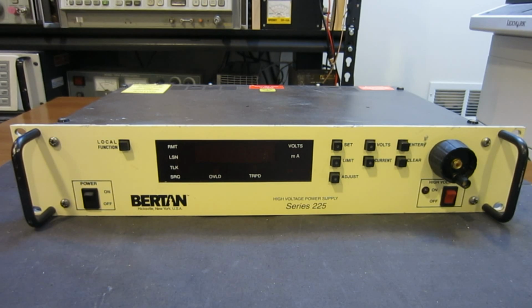Now, before I get started, I would like to stress that this is a high voltage power supply and we are dealing with potentially lethal voltage here. For someone who is not familiar with high voltage circuitry, I would highly recommend that you do not attempt to disassemble or play with this kind of equipment. Now, that said, for this one, it is relatively safe as the output current is limited to just above 1 milliamp. So even though the voltage could be very high, the actual current delivered would be relatively low. So you could, in theory, get a very nasty zap or shock if you accidentally touch the output, but it would probably not kill you. Anyway, you've been warned.